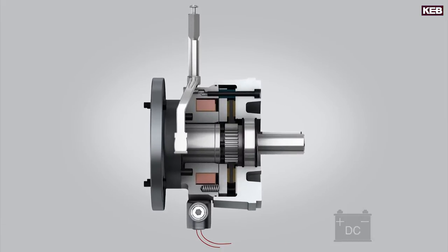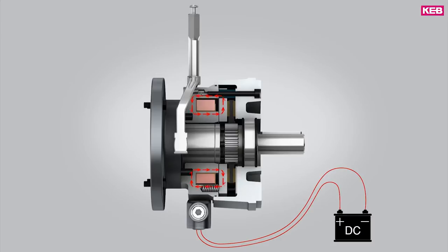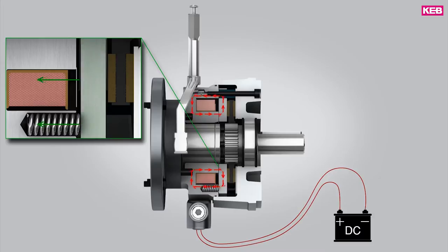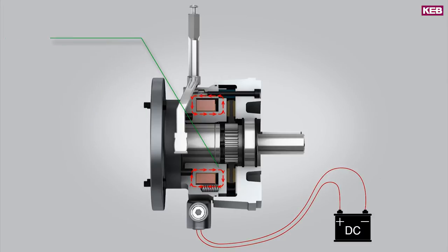Here's how the brake works. When a DC voltage is applied to the magnet coil, a magnetic field is created. The magnetic force pulls an armature across a small air gap and compresses multiple springs embedded in the magnet housing.